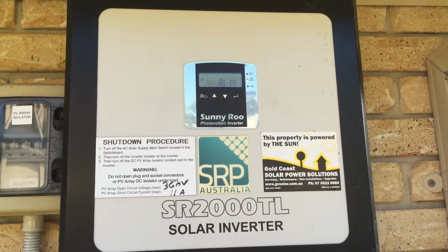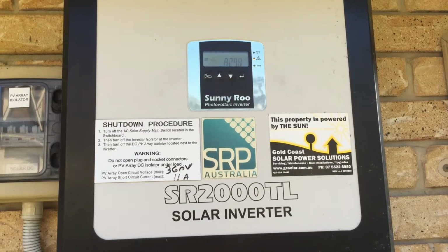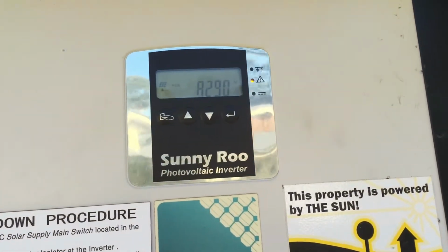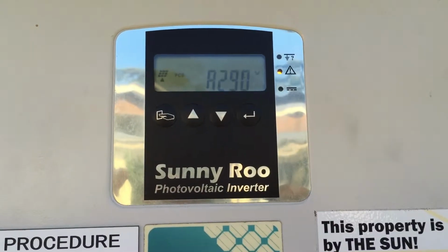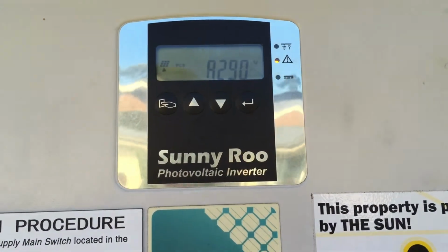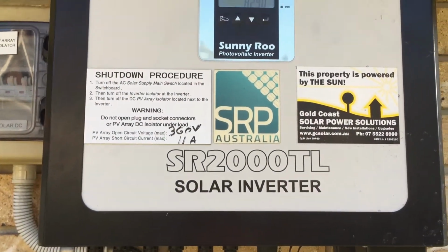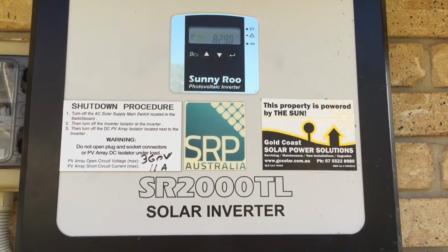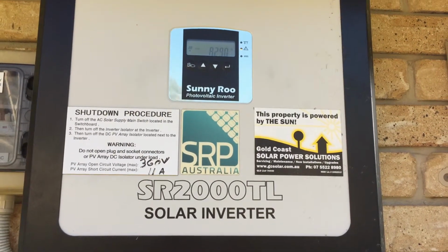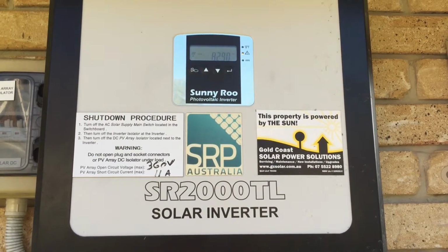Okay, so here today we have a Sunny Roo SR2000TL solar inverter, and you can see on the display of this one it's actually coming up with an AL14 error code. Now AL14 error code means there's been a problem with the utility. The utility or the waveform has failed.